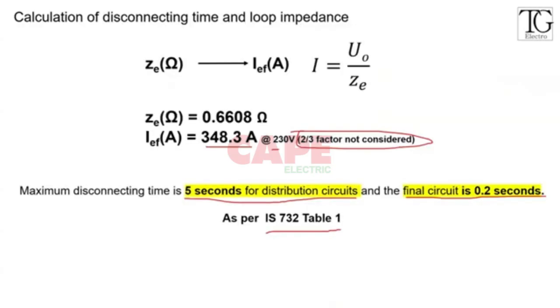It is mentioned clearly in IS 732 table 1. And if you go a little bit above IS 732 table 1, they have given a lot of text on what a distribution circuit is. This is for a TN-S system. So if you have a TT system, where you put an earth electrode, the disconnection time is going to be much less.